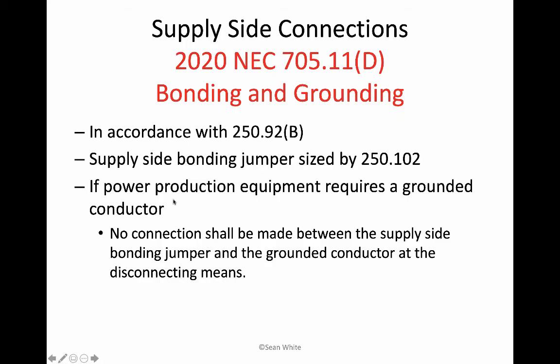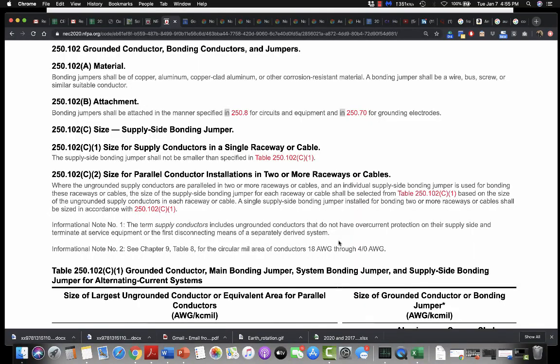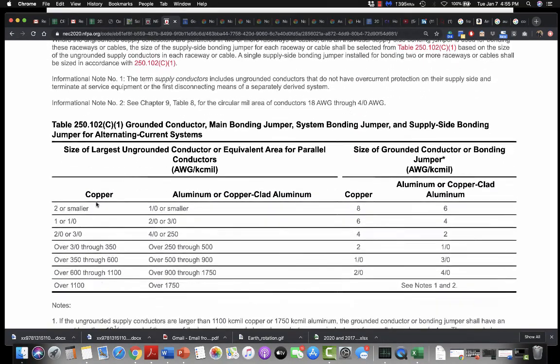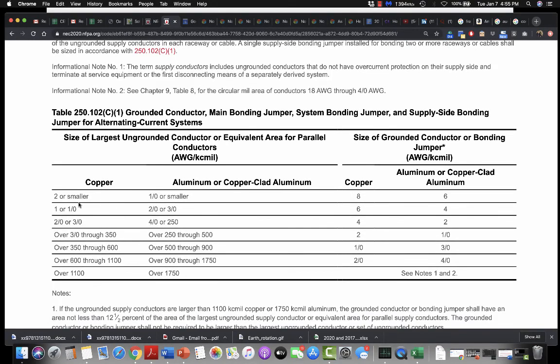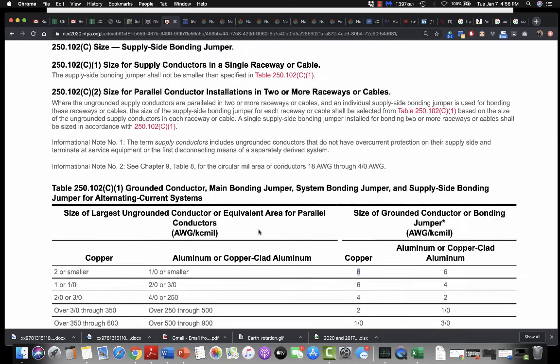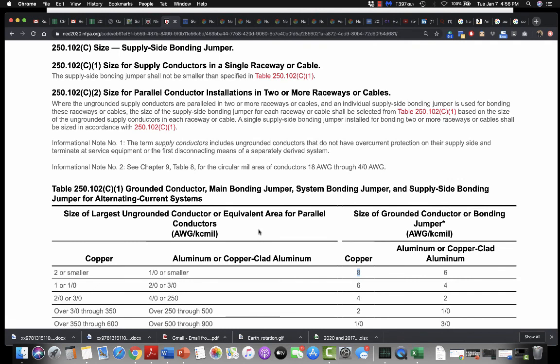Supply side bonding jumper now. We've got to look at that when we're doing a supply side connection. Supply side bonding jumper is sized in 250.102. And here it is, 250.102. And we can see that there's a table down here. It's showing you the service's largest ungrounded conductor, and it's kind of like that table we were just looking at, 250.66. But we can see over here, if it's 2 or smaller, hey, it's an 8. It's like the same size. So just check that out too for doing a supply side bonding jumper.